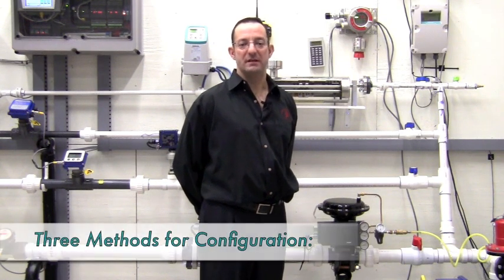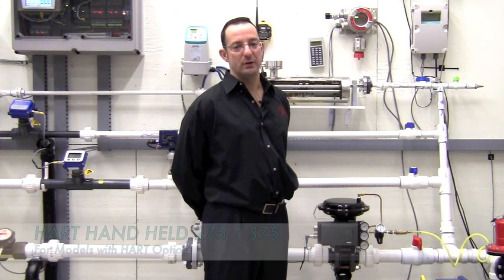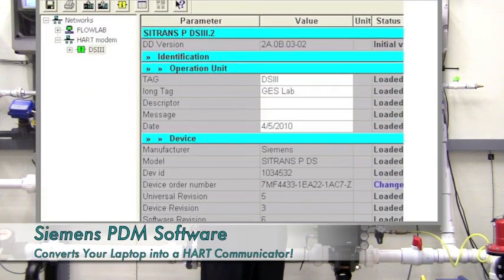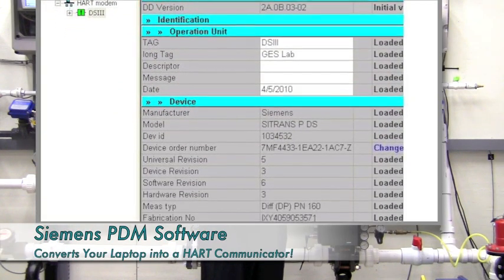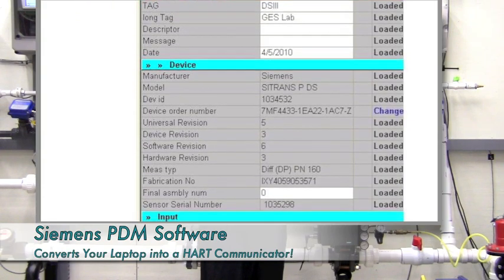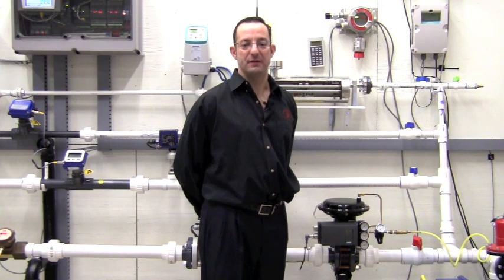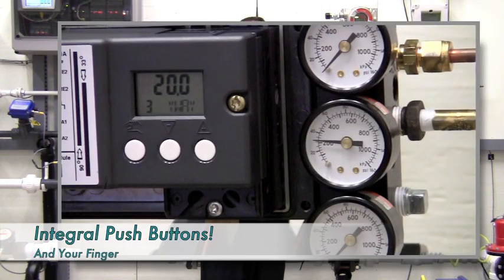The PS2 can be configured in at least three different ways. You can configure the unit with a HART handheld communicator. You can also use our PDM software package, which lets your laptop configure any HART protocol device on the market for under $500. But the simplest way to configure the PS2 is with the push buttons on the front of the unit and your two fingers.